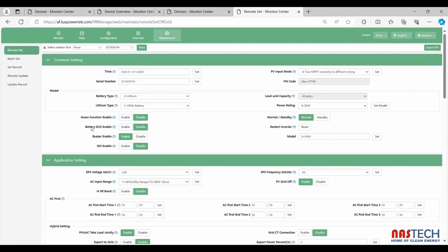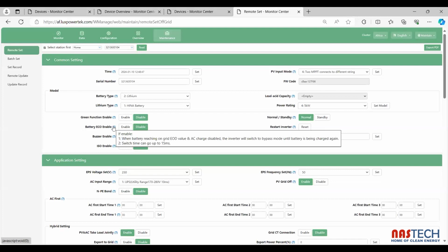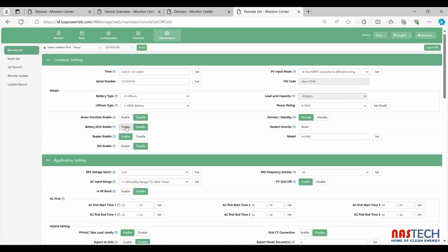Battery eco. So battery eco is if your battery SOC went down to a certain level, it will start charging itself. So when the battery went down to the on-grid EOD, the AC charge and the AC charge is disabled. Once you have this feature enabled, it will automatically start charging at that point. Buzzer enable, ISO enable. This is PV ground fault circuit interrupter. Many times the default is that this is disabled, and then if you have PV, you'd want to enable this.